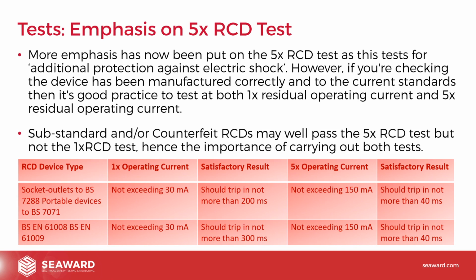So, the 5 times RCD test. More emphasis has now been put on the 5 times RCD test, as this tests for additional protection against electric shock. This is very much something that's come out of the 18th edition. They've really been hammering the importance of doing 5 times testing on RCDs, because if the RCD is there to provide additional protection against electric shock, that means it's going to be high currents. It means it's got to work at this 5 times rating. So with fixed wiring testing in the 18th edition, they've really switched round onto 5 times testing being the most important test. You must do 5 times testing.